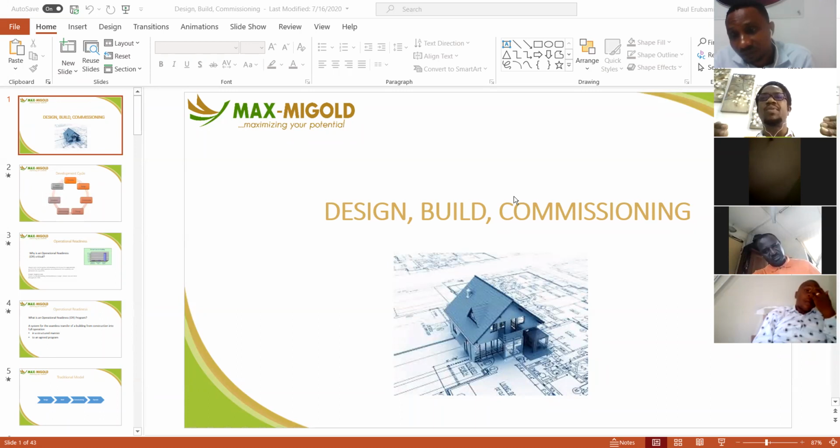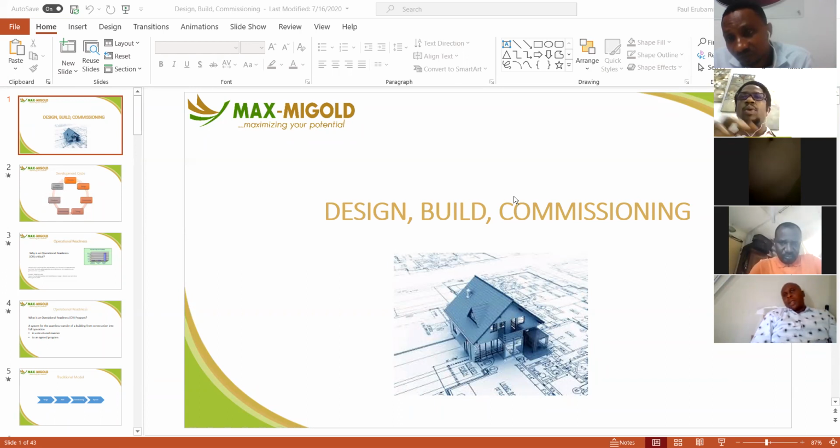And then finally, this is also very important, and many of us overlook this: building fabric and structure, our window insulation integrity, our doors and walls insulation integrity. If you have an air conditioner in a space, the AC's work primarily is to keep that space's temperature and air conditioned to the settings you require from it. But that setting is very different from the reality outside. Outside could be hot, but you want to cool that space. If you've provided connections through openings in windows or glasses that are too thin, not double glazed, for example, or walls where you can feel the cooling from outside, what you are doing basically is trying to cool the garden. And there's no way the AC can be big enough to cool your garden. So sometimes your air conditioning capacity can be limited by what you have created as access for the cooling to the outside spaces.